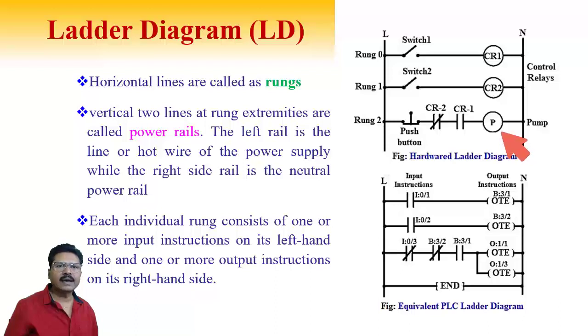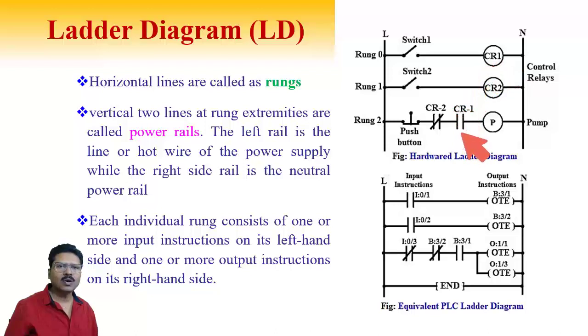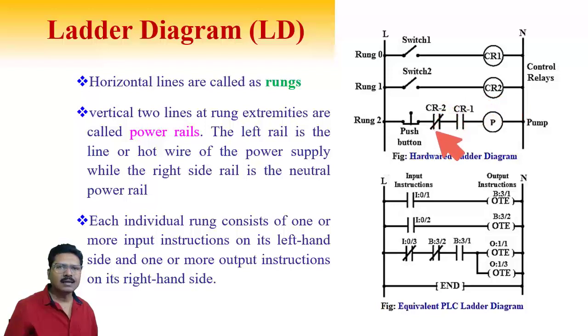How this relay logic works: when the start switch is pressed, relay coil CR1 is energized, and a normally open contact from CR1 is taken as a hold contact. When the stop switch is pressed, relay coil CR2 is energized, and its normally closed contact is taken — so when CR2 is energized, this provides logic zero. The push button is a normally closed contact.